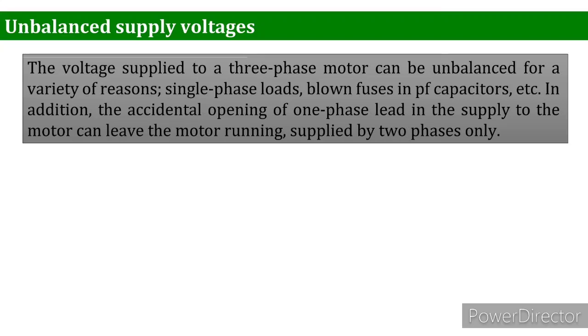It might seem that the degree of voltage imbalance met with in a normal installation would not affect the motor to any great extent. Similarly, it should be remembered that it is not the unbalanced voltage which is important, but the relatively much larger negative sequence component of the unbalanced current, because we all know that the negative sequence component is not a good friend of the devices we have. The major problem it causes is excessive heat, and also the wastage of electricity. So we have to avoid this unbalanced supply, especially in our three-phase system.